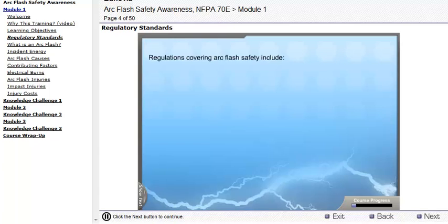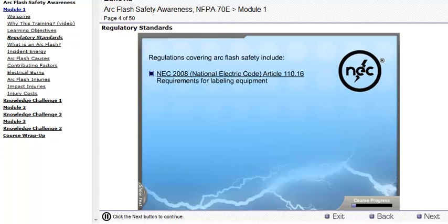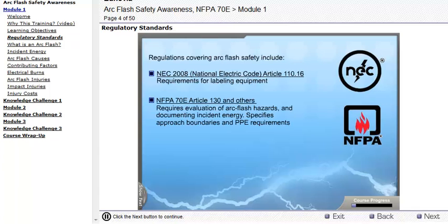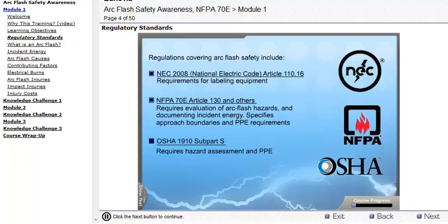Regulations covering arc flash safety include NEC 2008 National Electric Code, Article 110.16, which specifies requirements for labeling equipment. NFPA 70E, Standard for Electrical Safety in the Workplace, Article 130, and others, which requires an evaluation of arc flash hazards and documenting incident energy. This standard also specifies approach boundaries and PPE requirements for different hazard categories. And OSHA 1910 Subpart S, which requires hazard assessment and use of PPE.